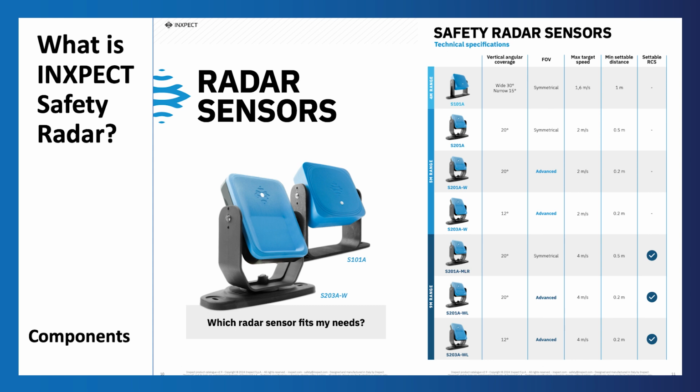It's great to have some of the AW sensors, where you're able to lop off what they call corridor view, which you can configure in their software, where you can take it down to a set width for the system instead of a conical output. That way, if you have, let's say, hard guarding on the left and right, a 2-inch mesh, you don't want it picking someone up on the other side of it, but you want this to go out for several meters looking out in the distance. It's easy to configure, where it'll just bring the sides in for a corridor.